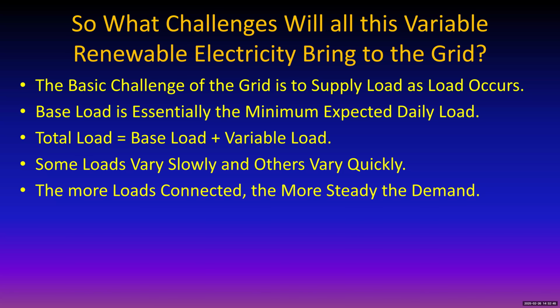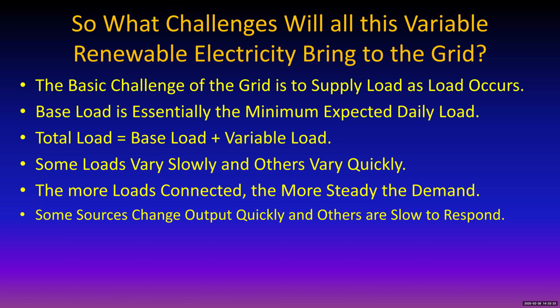In any case, the more loads that are connected, the more steady the demand. One illustration is how you size the service for a large residential building - you'll see they have demand factors, so if you've got 50 units in that building, the demand is down to about 30% of what it would be if you had 50 of them all by themselves. This applies to a neighborhood too, because not everybody runs their stove, air conditioning, or water heater at the same time. So the more loads connected, the more it tends to level out the demand.